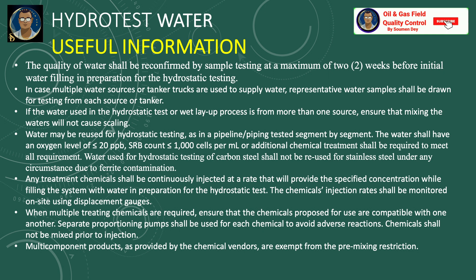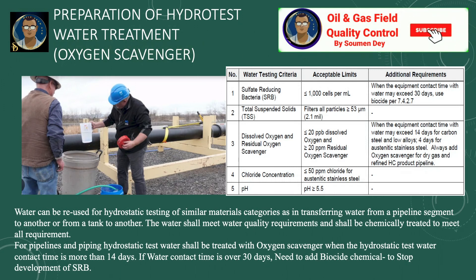Any treatment chemicals shall be continuously injected at a rate that will provide the specific concentration while filling the system with water in preparation for the hydrostatic test. The chemical injection rates shall be monitored on site using displacement gauges. When multiple treating chemicals are required, ensure that the chemicals proposed for use are compatible with one another. Separate proportioning pumps shall be used for each chemical to avoid adverse reactions, and chemicals shall not be mixed prior to injection.